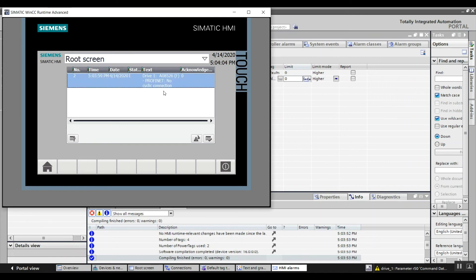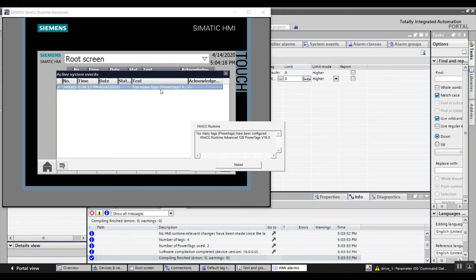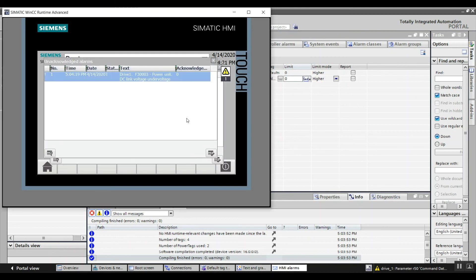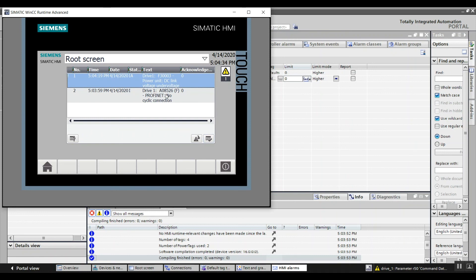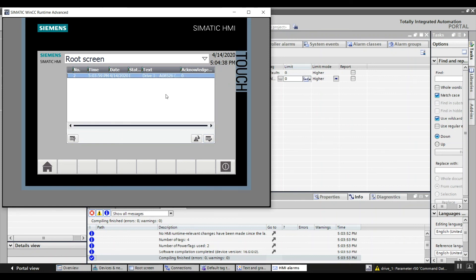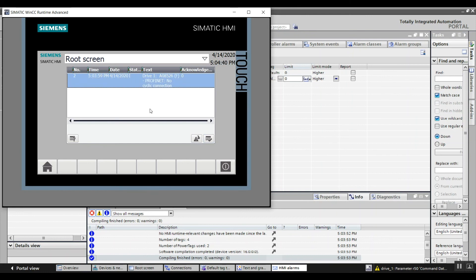Right now I've got a PROFINET error or alarm on my drive, and you can see that displayed. I'll run my drive and create a fault. I've got a DC link under voltage fault because I turned my drive off and back on quickly while it was running. I can't acknowledge these faults on the HMI until I acknowledge them in my drive. There — the DC link under voltage fault went away in my HMI.